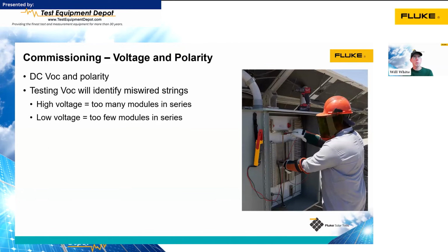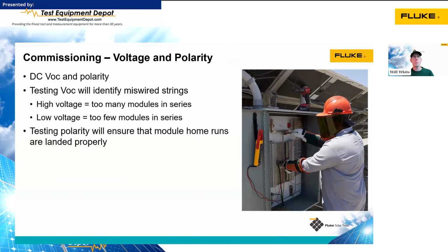Now, during commissioning, after everything has been installed, but before we've started to energize things, we're going to do voltage and polarity testing. Voltage is to determine that we have the right number of modules connected in series. So if we have too high voltage, that means someone connected too many modules in the string. If the voltage is too low, we have too few modules in the string. And usually those two problems are paired together because someone put too many modules in one string and not enough in another. We're going to test polarity before we commission the system, before we close any fuse holders, to ensure that the positives are all connected to positive and the negatives connected to negative.